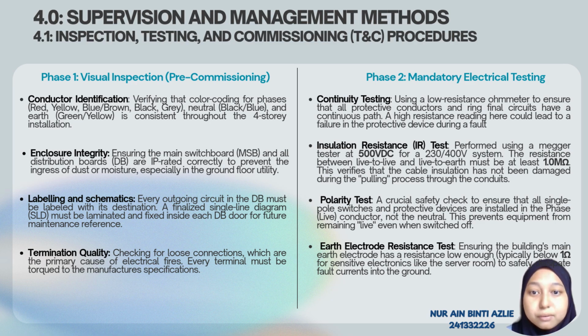First phase is a visual inspection. Before any circuit is energized, a comprehensive visual audit is conducted to identify physical non-conformities. First is conductor identification, verifying that the color coding for phase is red, yellow, blue or brown, black and gray. For neutral it is black or blue, and earth is green or yellow. It must be consistent throughout the four-story installation.